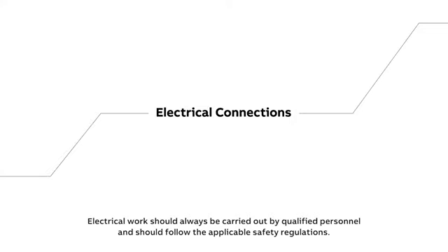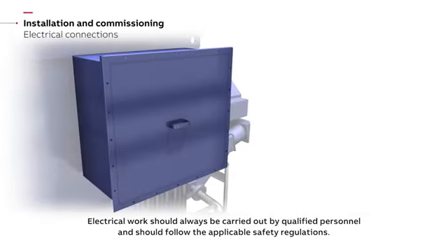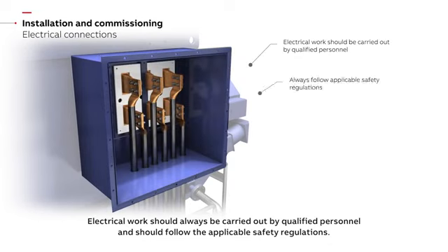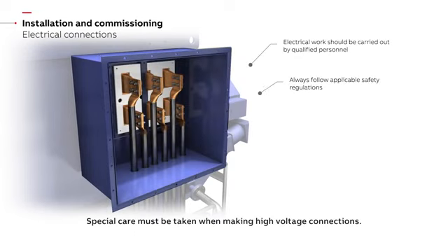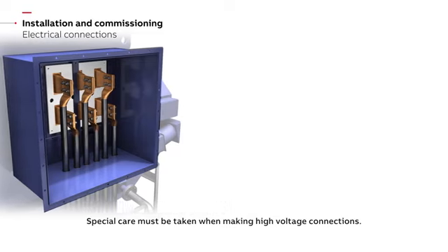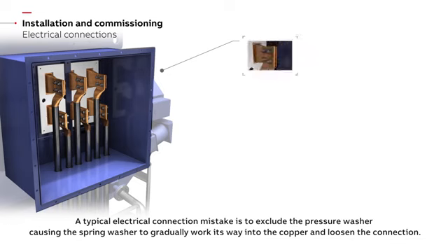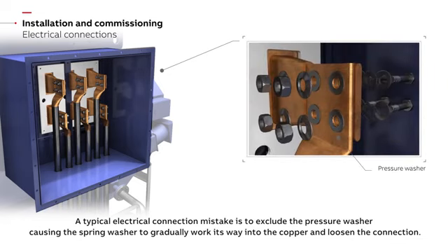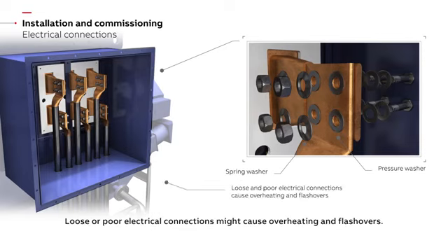Electrical work should always be carried out by qualified personnel and should follow the applicable safety regulations. Special care must be taken when making high-voltage connections. A typical electrical connection mistake is to exclude the pressure washer, causing the spring washer to gradually work its way into the copper and loosen the connection. Loose or poor electrical connections might cause overheating and flashovers.